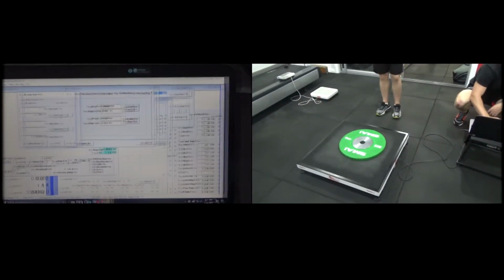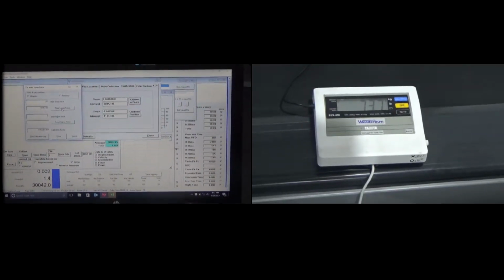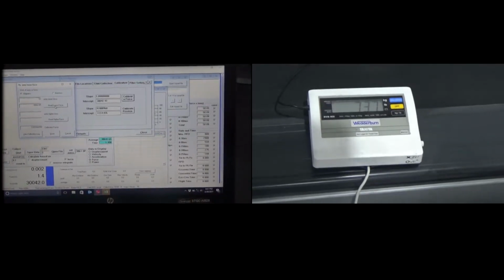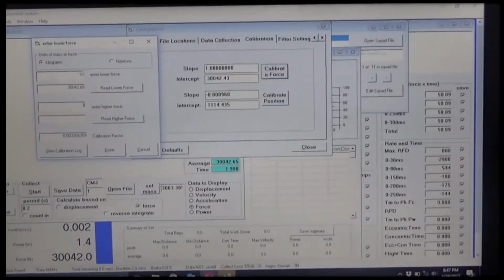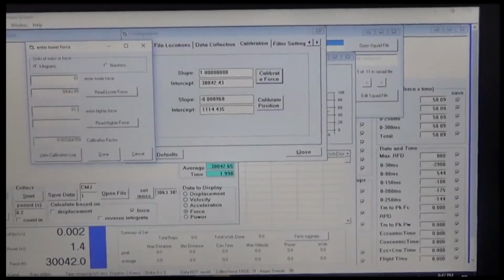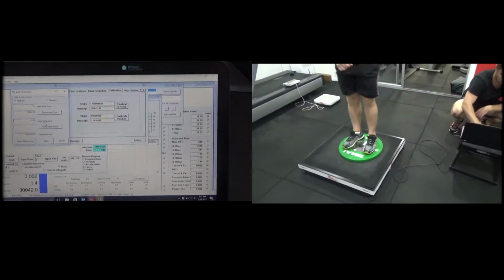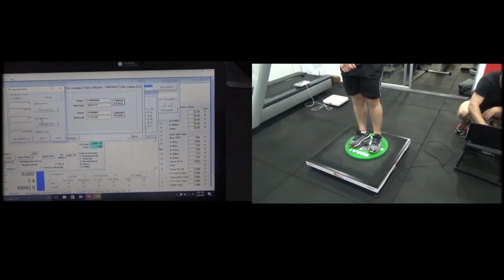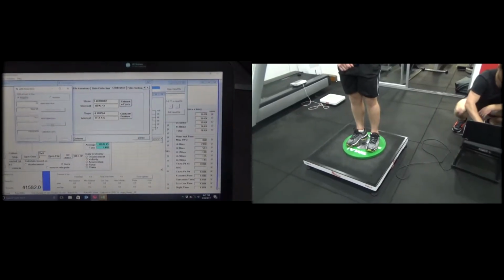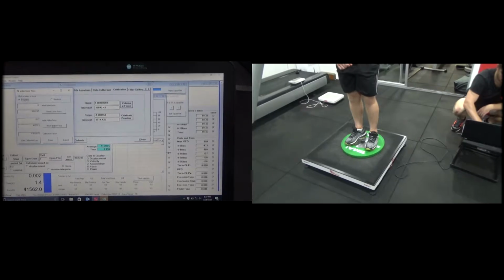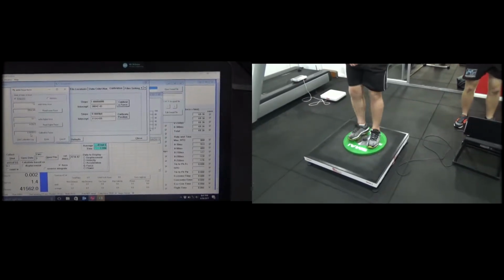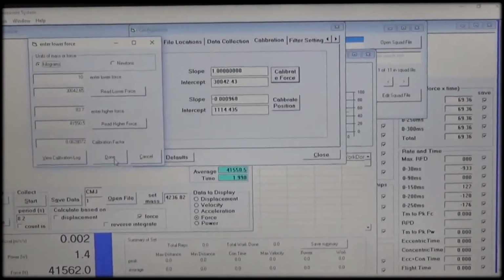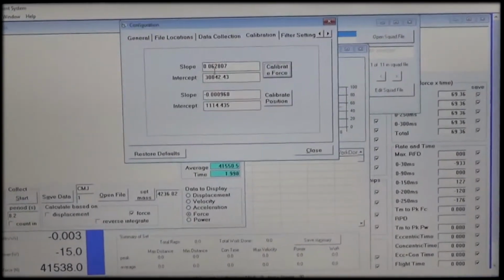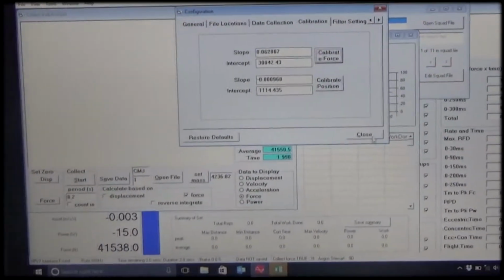We're also using an athlete that is 73.7 kilograms, so we make that 83.7 here for the enter higher force. We get the athlete to stand on the force plate and we hit Read Higher Force. That gives us a calibration factor of 0.062 and we click Done. 0.062 here, so we close the calibration.